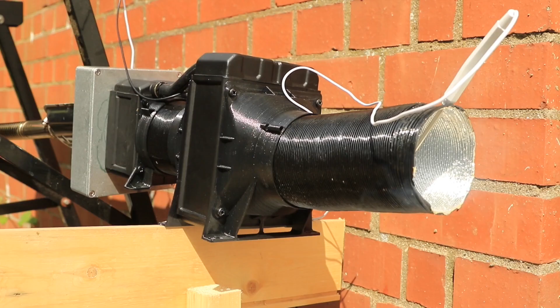So we're just now looking underneath our first heat exchanger. You can see now we're starting to get some drips, and what this is, as the diesel fuel is burnt, one of the byproducts is water. So the water, it's been obviously turned into a gas when it's been burnt. That flows down the exhaust. As soon as it hits the colder coils of the heat exchanger, it then condenses and will turn back into water, and that's what we can see dripping out of the bottom of our heat exchanger. Not necessarily an issue, nothing to be concerned about, nothing's melting or anything like that, just something to be aware of if you're trying to reclaim your exhaust gases.